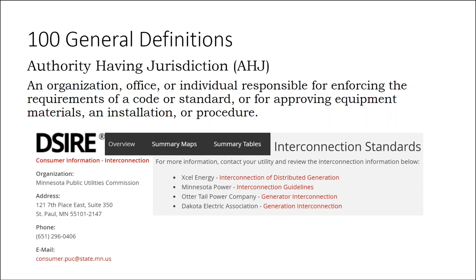And for supply cables, which might need some mechanical protection, like being in metal conduit, the authority having jurisdiction may say, you know what? Code says DC wiring has to be in metal conduit for protection, but it doesn't say whether that could be metal clad conduit or EMT conduit. And often in densely populated buildings that are multiple stories tall, if there's a requirement for physical protection, they'll want you to use even more robust metal conduit, like rigid conduit or intermediate metal conduit, which we'll get to.